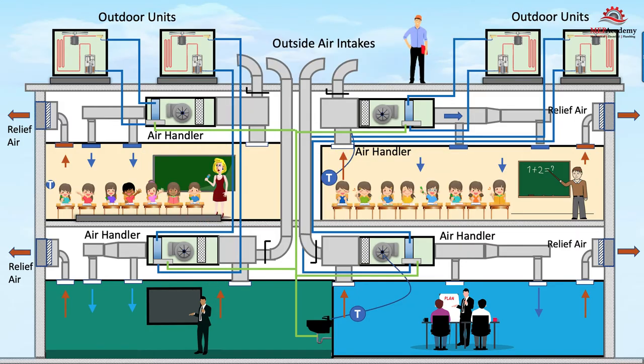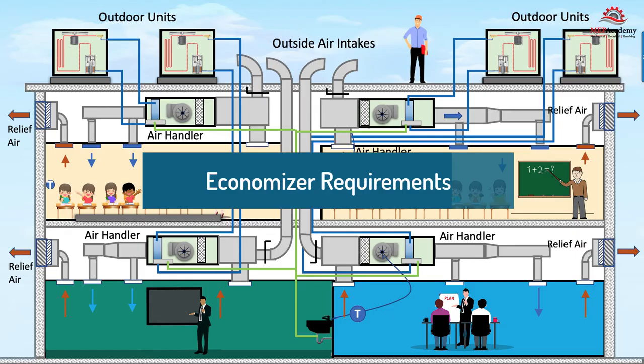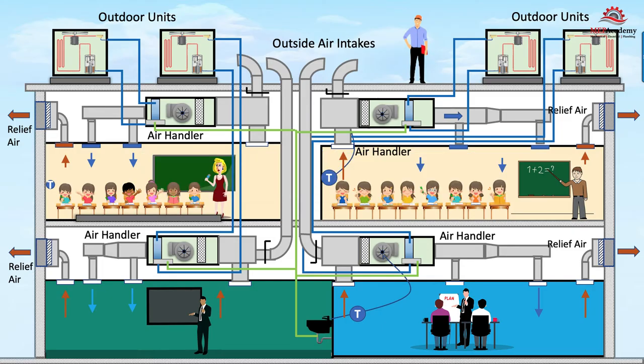The lowest first-cost option would be to duct the ventilation air individually from each indoor air handler. This would require additional energy from the air handler fan and coil, and a lot of small ducts running through the building from each air handler — unless an economizer is required for your indoor air handler because it meets the threshold of your energy code, in which case the ducts would be much larger and may not make sense. As shown before, each air handler has a condensate drain going to the tailpiece of the sink.